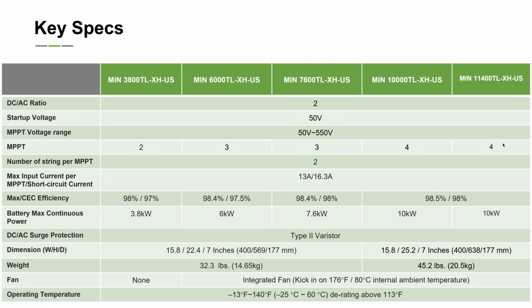For each MPPT, the number of strings parameter is 2. The maximum input current per MPPT is about 13 amps. Usually that's only for 1 string per MPPT, but if you're using high voltage PV, you can have two strings per MPPT. And you can see the max efficiency for our size is about 98%, which is really high in the market right now.